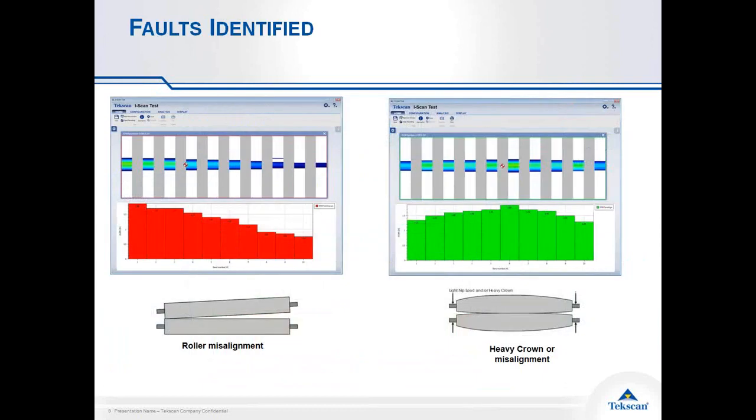Now as we look at some of the faults that we discussed at the beginning of the presentation, you can see the software will give you a clear representation of what kind of fault you're looking at, whether it's the roller misalignment we're showing on the left where we can see the center of force is very much on the left side of that setup, and the operator has a clear indicator of what adjustments need to be made.